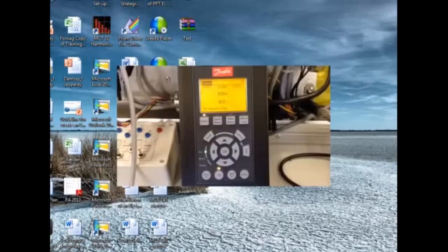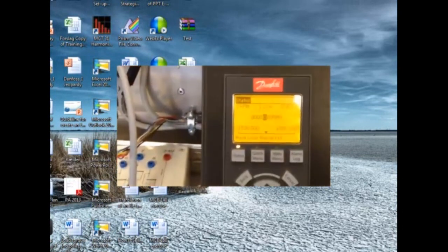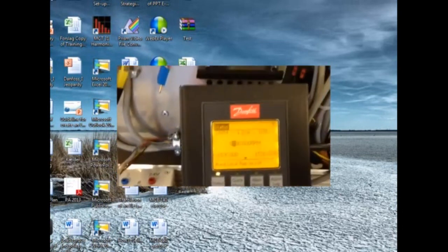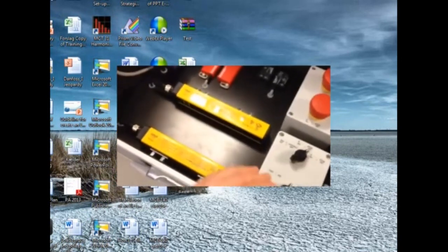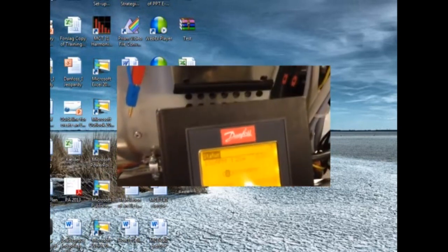I will now shortly demonstrate what we have written into the option. The light curtain is our SLS, and by moving into the light curtain it will ramp down to 150 RPM. By leaving the area again, it will automatically ramp up again.